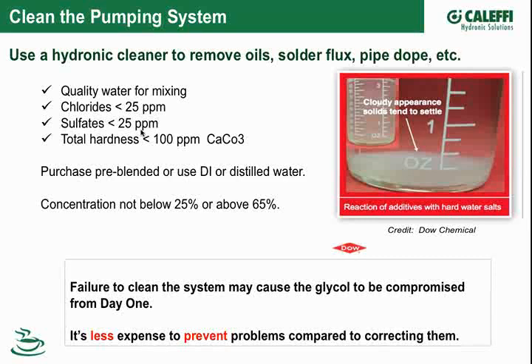You can test hardness pretty easily, but how would a contractor on the job know if chlorides and sulfates meet spec? At some point it usually comes down to either buying pre-blended glycol, or making sure you're using a proper DI or distilled water if you're blending on the job. Anything I'm missing there?